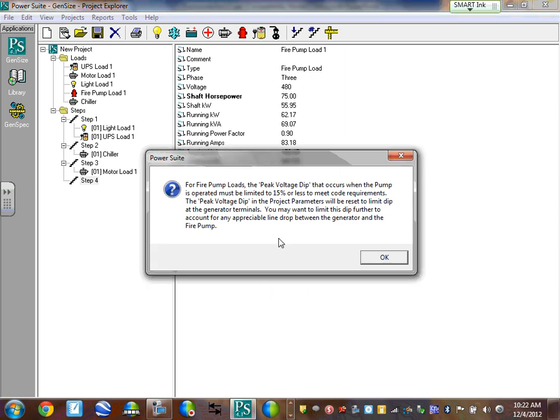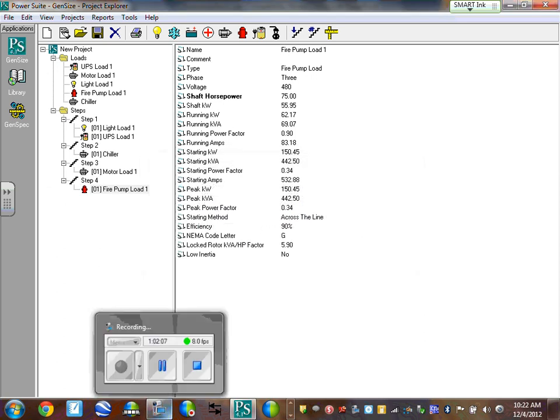Okay, they do know. For fire pump loads, the peak voltage dip that occurs when the pump is operated must be limited to 15% or less to meet code requirements. The peak voltage dip in the project parameters will be reset to limit dip at the generator terminals. You may want to limit this dip further to account for any appreciable line drop between the generator and the fire pump. Good comment. Okay.